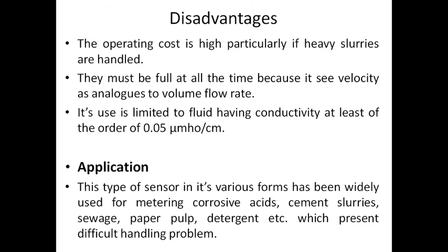Then the disadvantages are that the operating cost is high, particularly if heavy slurries are handled. They must be full at all times because velocity is analogous to volume flow rate. Its use is limited to fluid having conductivity of at least the order of 0.05 micromho per centimeter.